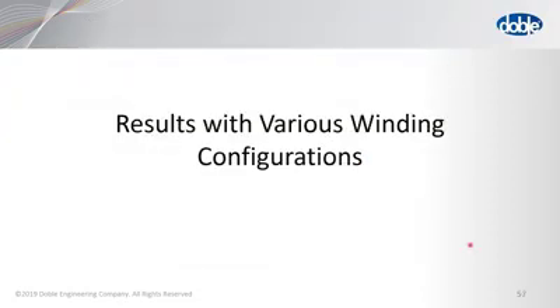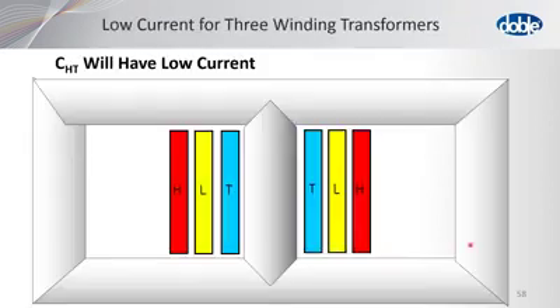So let's look at some results with various winding configurations. These are quite interesting. In this particular case, we show that the CHT will have a low current. Now, why is this? During the CHT test, you're energizing the tertiary winding and trying to measure to the high voltage winding. Well, notice that the low voltage winding is in the way. And in that particular test, the low voltage winding is grounded. So in UST, the low voltage winding being grounded, the current trying to get to the high voltage winding is guarded away. It is not measured. So it almost makes the high voltage winding disappear.